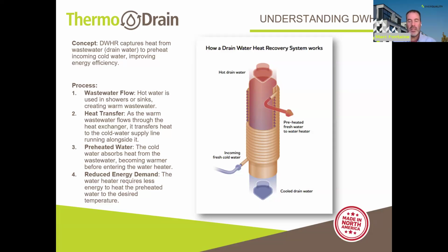So the way that this device works is that as hot water goes down the drain, it goes through the drain pipe of the drain water heat recovery unit, and then we have cold water coming into the coil portion. And as that cold water goes up in the coil, there's a heat exchange process that occurs where the heat from the hot water going down the drain transfers across the copper cross section and then heats up the cold water. So we end up with preheated water coming out of the DWHR unit. And so now that preheated water we can use to supply a hot water heater, for instance, or the cold side of a shower fixture. And we'll get back to that a little later on.